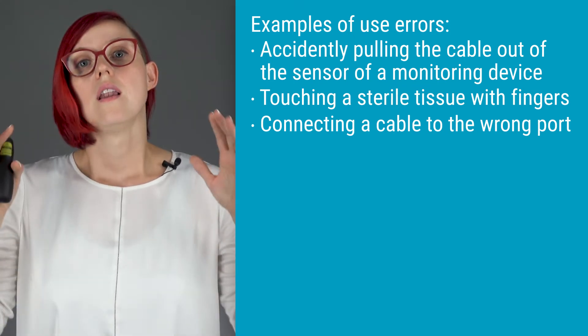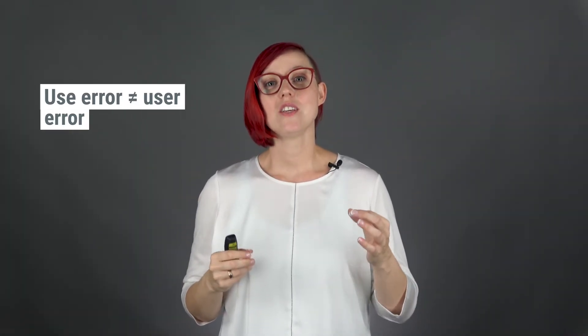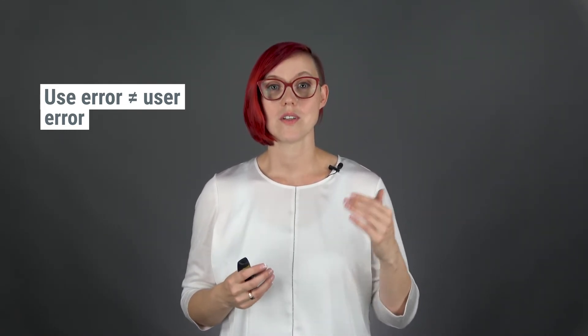There are many different potential use errors. And please note — it's not called a 'user error.' User error implies it's the user's fault, but it's most definitely not always the user's fault when there's a use error. Another important term is 'hazard-related use scenario,' which can be challenging for those not familiar with risk management. A hazard-related use scenario is a hazardous situation that occurred as a result of a use error.